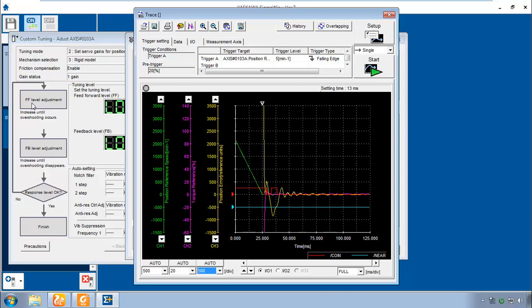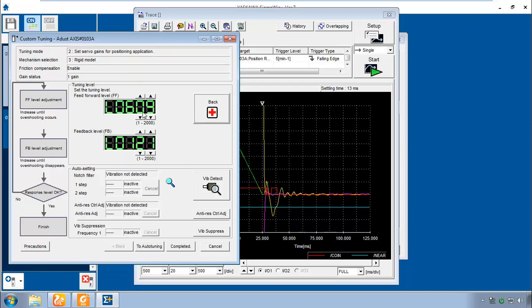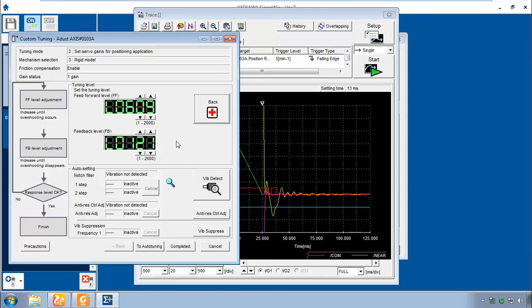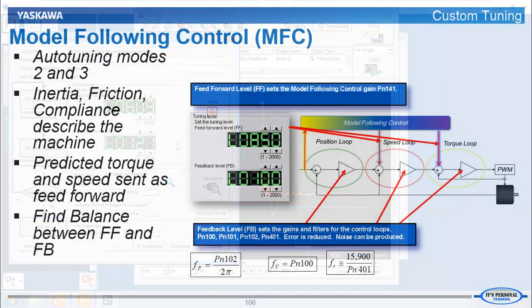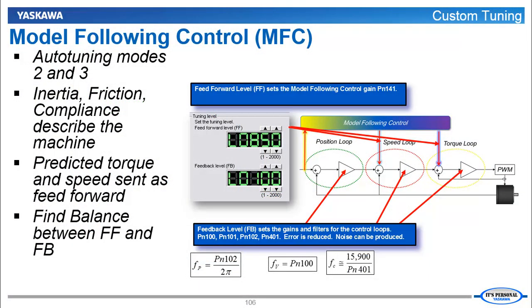And that's why the flow chart here says increase the feed forward until overshooting occurs. Looks like that's already happened. And then increase feedback level until the overshooting disappears. This is the overshooting that we need to disappear by increasing the feedback level. The reason that this will work can be understood by examining how these tuning levels affect the Torque, Speed and Position Loops. And it has to do with Model Following Control used by Tuning Modes 2 and 3.